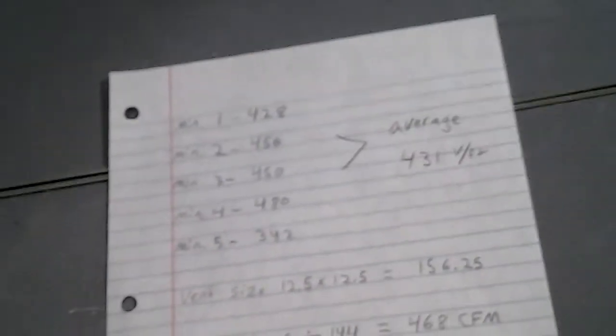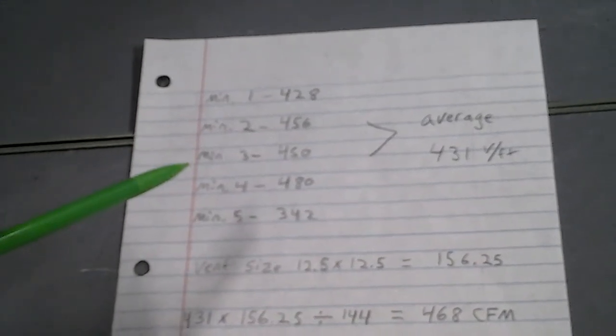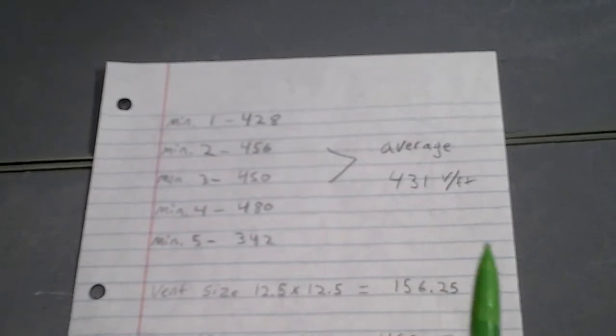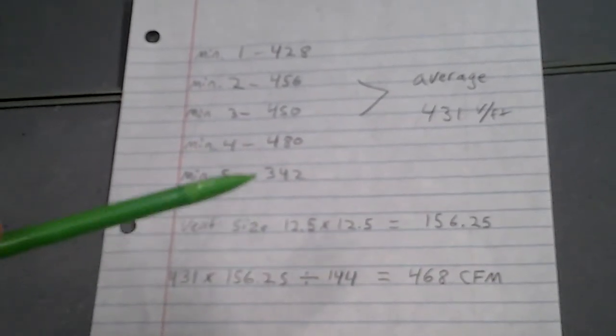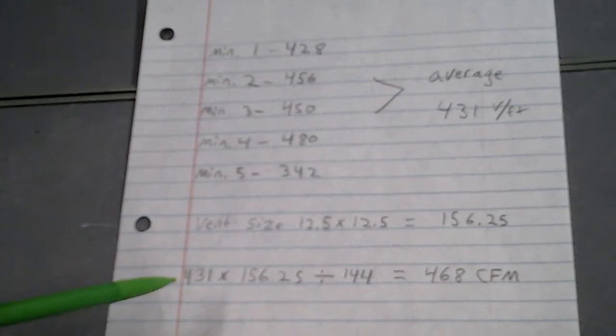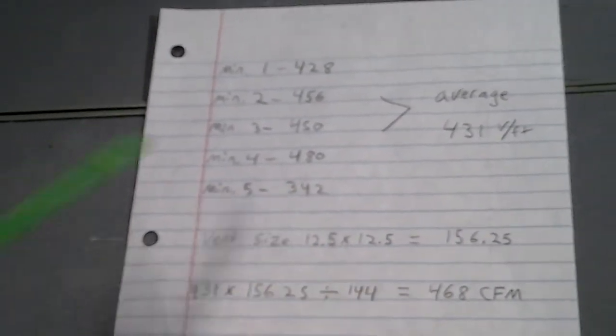So we're back with the numbers that we got. Minute one: 428 feet per minute. Minute two: 456. Minute three: 450. Minute four: 480. Minute five: 342. Our average number is 431 velocity per foot. Our vent size was 12.5 by 12.5, giving 156.25 square inches. So we take 431 times 156.25 square inches, divide that by 144, and we got 468 CFM.